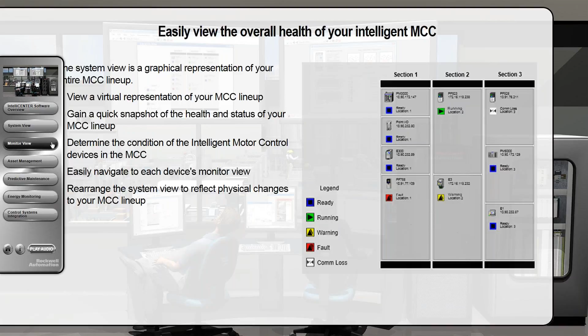As you navigate to those devices specifically, you have a monitor view of each device. Here I'm showing the E300 overload relay. Here you have its own realm and point of view for changing the device information you want to receive, understanding what your I/O data looks like, your limits, high-highs, low-lows, and parameters that are particularly important, such as FLA setting, trip class, trip enable, warning enable, and trending that information in real time.